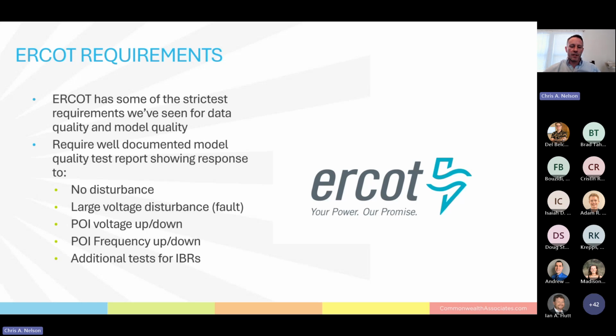For inverter-based resources, there's probably about double that many things they do. They have a lot more ride-through requirements and things like that, and a lot of very specific tests at ERCOT. I think they need their steady state model to be pretty detailed too. I believe ERCOT is one of the ones requiring a PSCAD model for inverter-based resources too, though it might be only specific ones. I don't think we had to do that — no, actually I take that back. I think it is all inverter-based resources, but the one we worked with on ERCOT was a conventional generator.